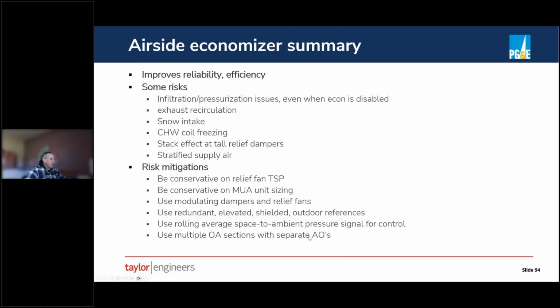Multiple outside air sections with separate analog output. So that deals with things like snow intake, stratified supply air, even this relief damper stack effect issue can be addressed by having the ability to control separate sections. You're going to have an outside air damper that's going to be sized for 100% of the air, but in the winter, you only want a tiny amount of outside air, typically because it's so cold that you mix your 0-degree outside air with 100-degree return air. You're mostly return air to get your, say, 75-degree supply air.